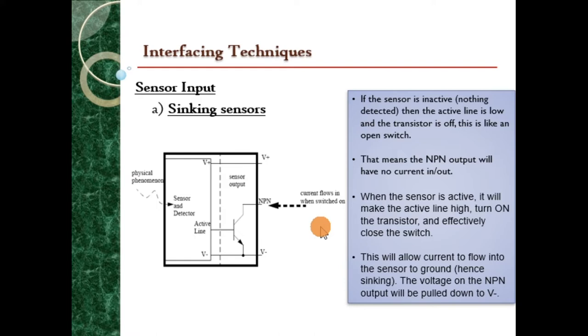When the sensor is active, it makes the active line high, and then it turns on the gate of the NPN, effectively closing the switch. This allows the current to flow into the sensor to the ground, hence sinking. And then the voltage of the NPN output will be pulled down to minus V.